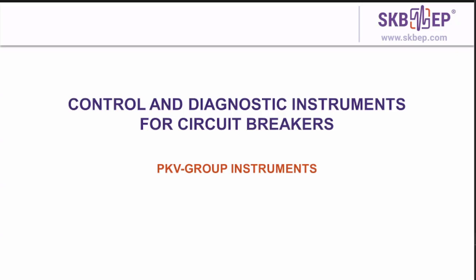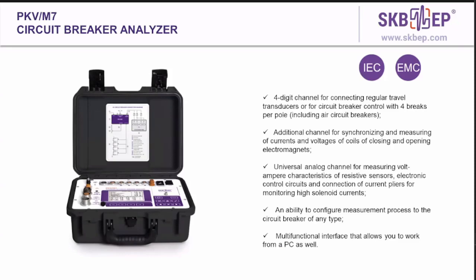Now we'll go further to our instruments and start with the PKV group of instruments, which are control and diagnostic instruments for medium voltage and high voltage circuit breakers. The first to start with is PKV M7. Its key features are it has 4 digital channels for connecting regular travel transducers or for circuit breaker control with 4 breaks per pole. Multifunction interface that allows you to work from a PC as well. Also, there is a possibility to transfer the data by USB flash card. Another important feature of it is the protective case with the ingress protection code 64.